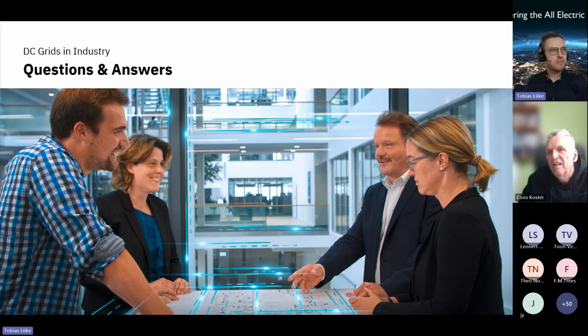It's actually a good question. I try to answer it from two perspectives: one is the manufacturer of components, and the other is the planner of the application. The planner, in my opinion, wants the biggest benefit out of a DC grid. If you double the voltage, you lower the losses by a factor of 4. So for me it makes total sense to go in all applications up to 1500 volts, that's a thesis from my side. On the manufacturer side, as we are, we need to look at the power electronics available that can handle 1500 volts, and there are only rare ones. So that could be, on the component side, a lack of technology. That's kind of answering your question.